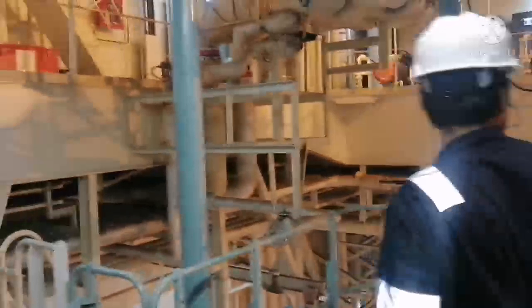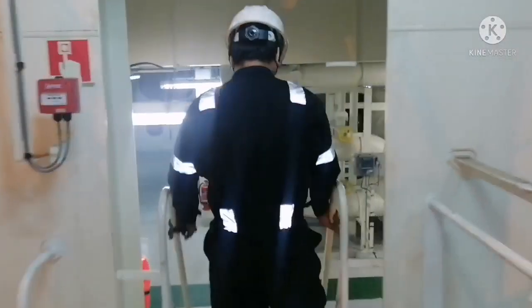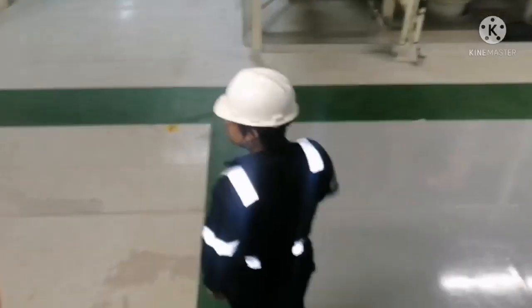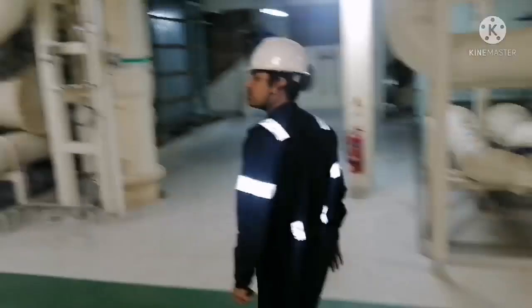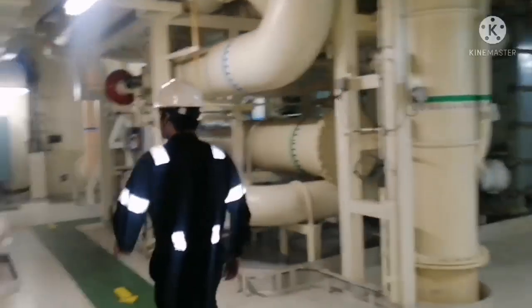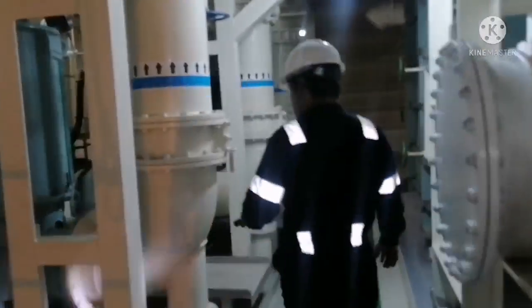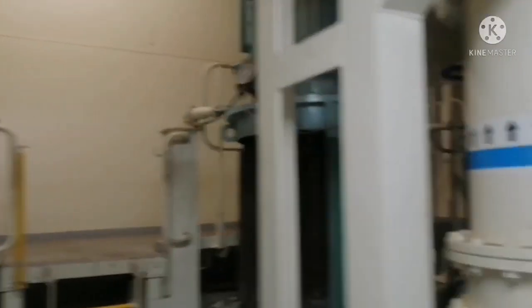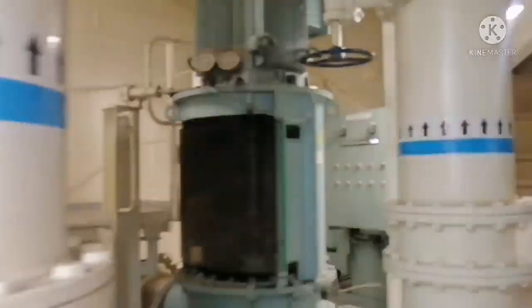This ship has 11 units, so check for all 11 units. Oh, okay, so I go down again to the bottom platform. This is your bottom platform, and this is your air LT cooler platform actually. So just check for any leakages over the pump. Just check for any leakages in the pipes, any leak in seals of pumps.